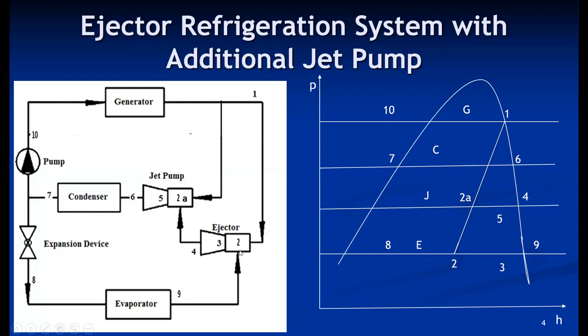This mixture from the ejector then enters the jet pump suction line. If the ejector outlet is directly connected to the condenser and the condenser pressure is high, there is a possibility of back pressure stopping operation. So the outlet of the ejector at point four is connected to the suction of the jet pump. The jet pump also has an intermediate pressure at point two-A. Points four and two-A mix at point five.